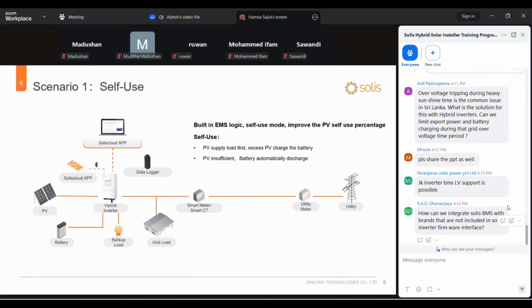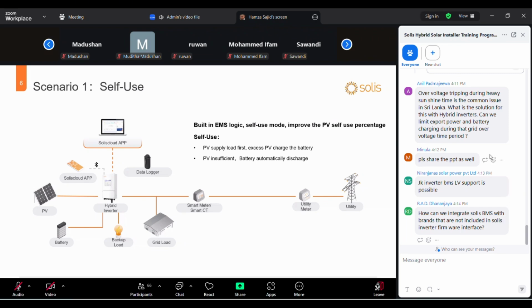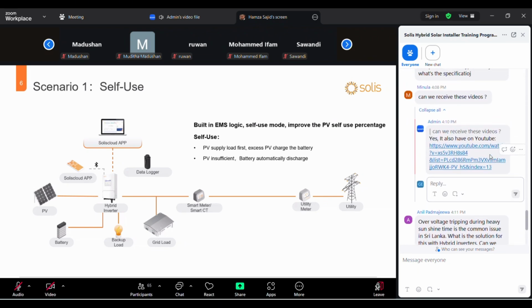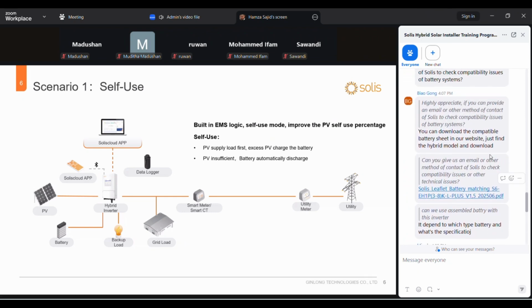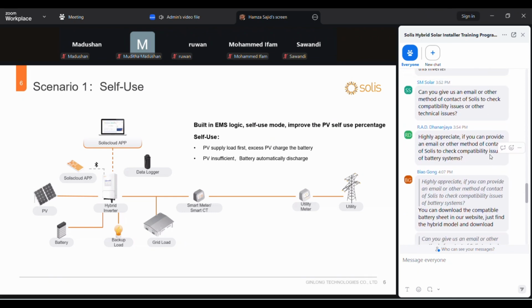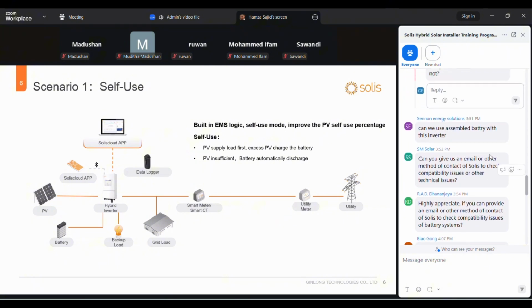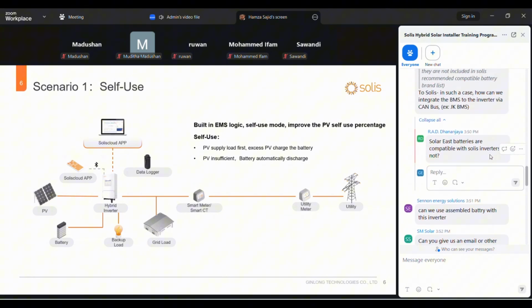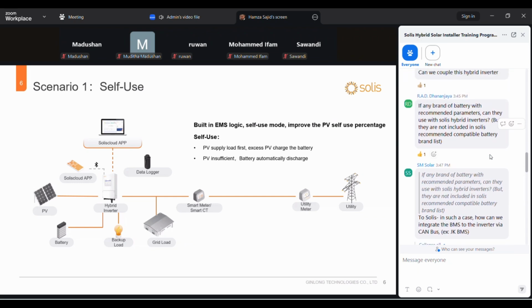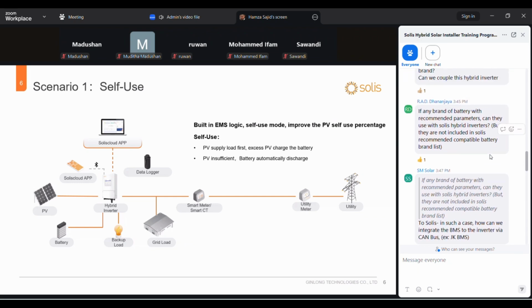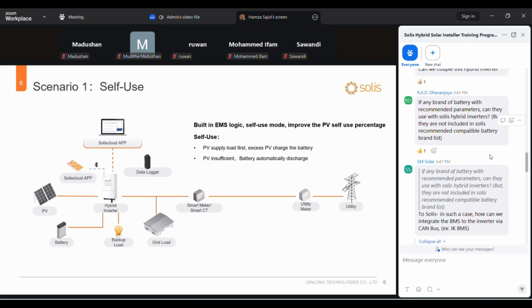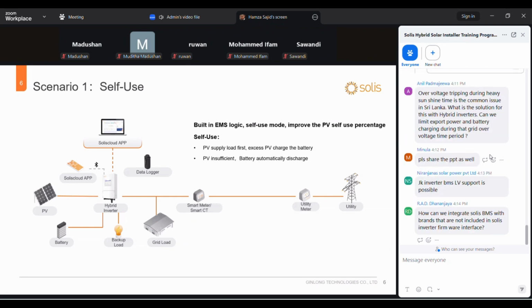There is a question from Anil. Over voltage tripping during heavy sunshine time is the common issue in the Sri Lanka market. What is the solution for this with the hybrid inverters? Can we limit the export power and the battery charging during that grid over voltage time period? Okay, if you know the specific time when the grid voltages are going to be high, you can set the time period according to that. You can even charge the battery, or you can also limit the export power.